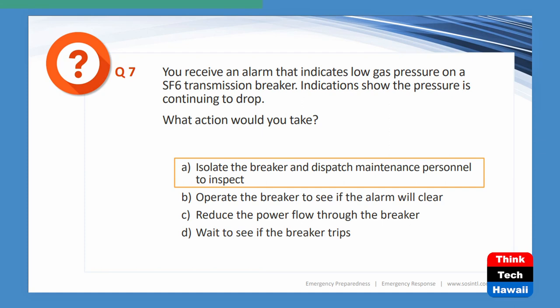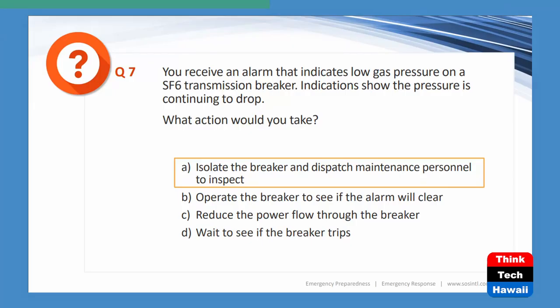So A, isolate the breaker and dispatch maintenance personnel to inspect. Okay. B, operate the breaker to see if the alarm will clear. Okay. No. C, reduce the power flow of the breaker. If you have a fault, it still won't function as needed. It may not function at all. You know, some of these breakers use compressed air or SF6 gas to actually operate. So that's another concern also. And the last one, D, wait to see if the breaker trips. And that's the worst possible solution.